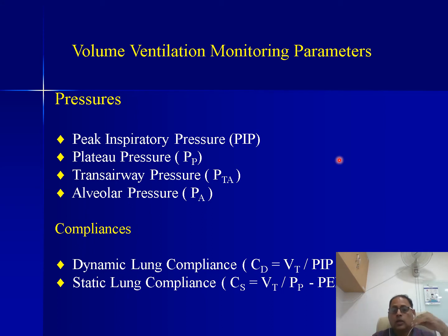So what will happen is there will be no gas flow, because you held the inspiration and you have not opened the expiration valve. So there is no gas flow, and the pressure in the airway as well as the alveoli becomes the same. This pressure is the plateau pressure, also termed the alveolar pressure, right? And then there is the transairway pressure, which is largely the difference between the PIP and the plateau pressure.